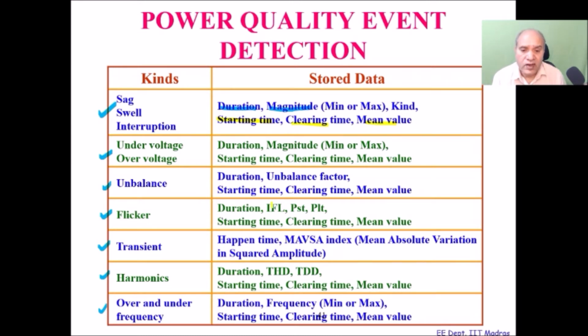In case of flicker, these are called IFL, PST and PLT. They are special indices for measurement of flicker, and there is a starting time and clearing time and mean value for this, okay? For transient, this is called mean absolute variation in squared amplitude, MAVSA. It is a special figure of index to measure the transient. It's called mean absolute variation in squared amplitude.